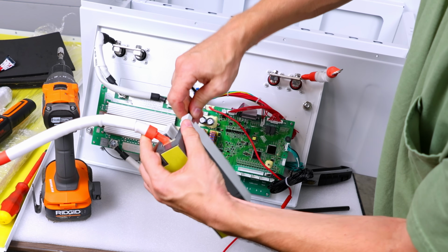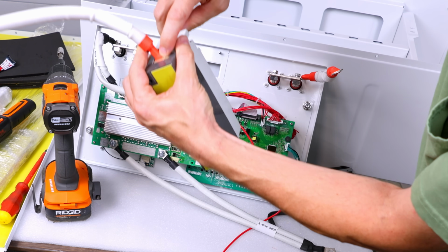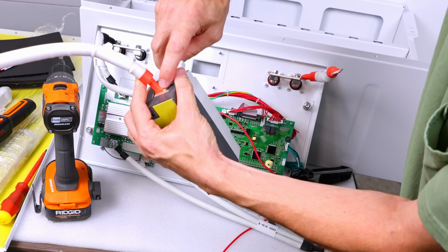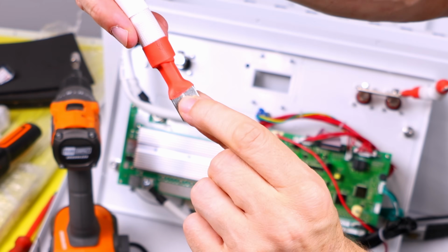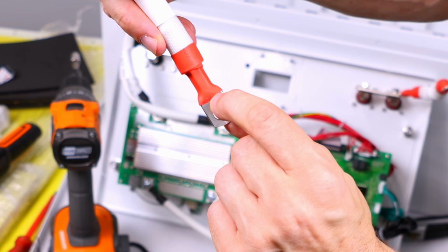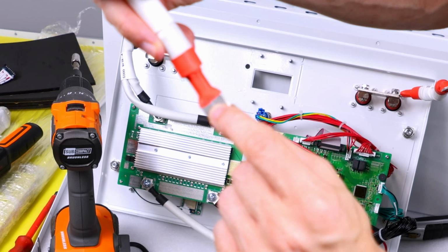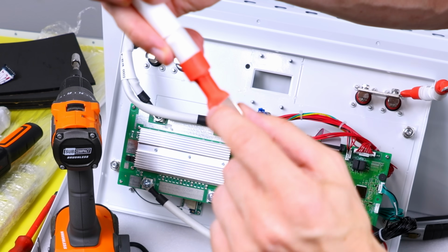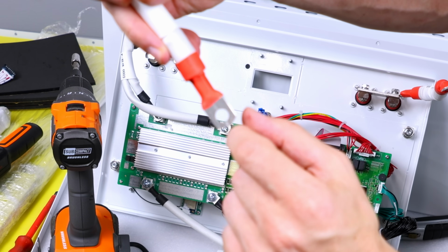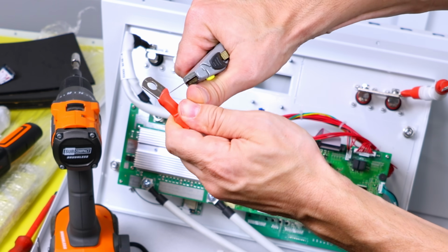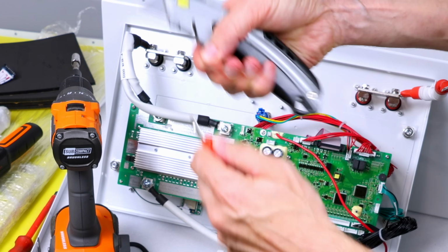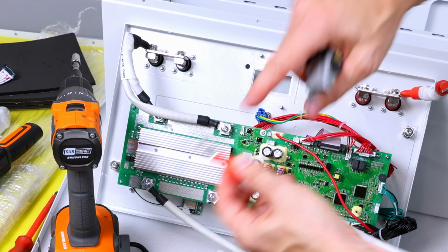I can clearly see there was insulation under that, and that's no good, you don't want that. You can see the insulation marked there where it was crimped down, and that prevents it from seating completely, and you'll have a chance of a high resistance connection there. So we'll cut that back. There's no need for the insulation to go all the way down like that. Just make sure the entire flat is free from insulation.